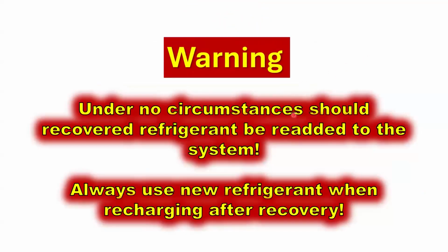Warning: under no circumstances should you re-add recovered refrigerant to the system. Always use new refrigerant when recharging after recovery. Always a good idea. We just don't know. Like I mentioned before, we've had cases of R410 being put in R454 units. So if you have something weird happening on an R454B system that's been installed for 6 months or whatever, and it's overheating with weird pressures and operation, that'd be another reason why you don't want to. You might want to pull and verify the charge, but unless you know 100% that's the correct refrigerant, don't put it back in the system.